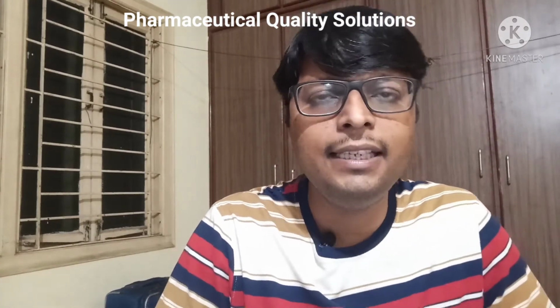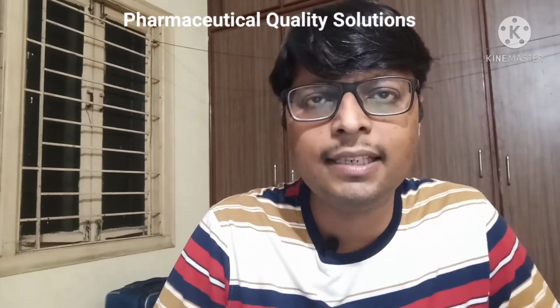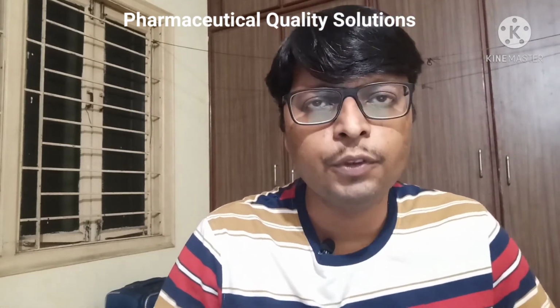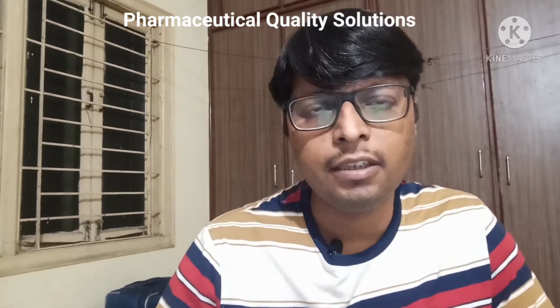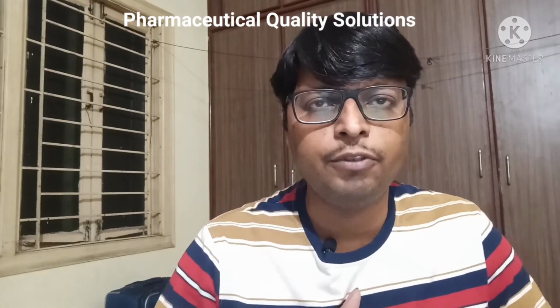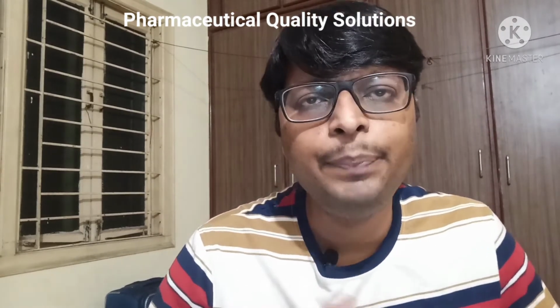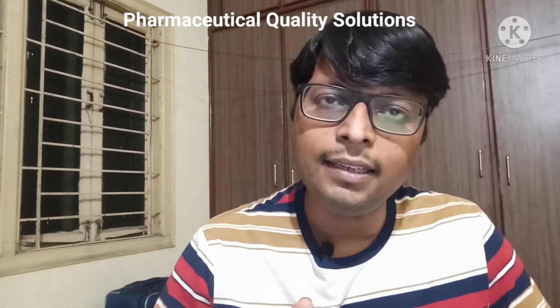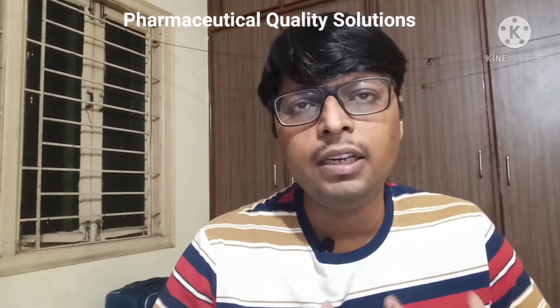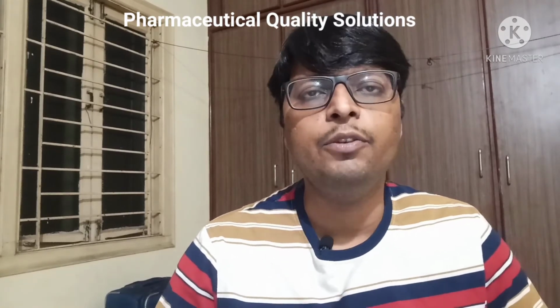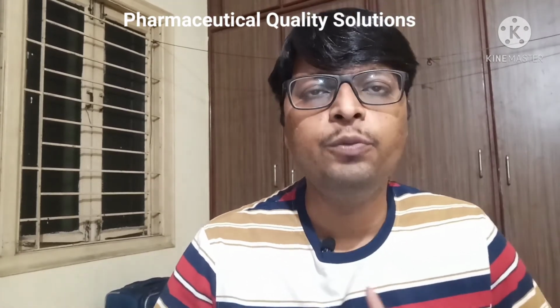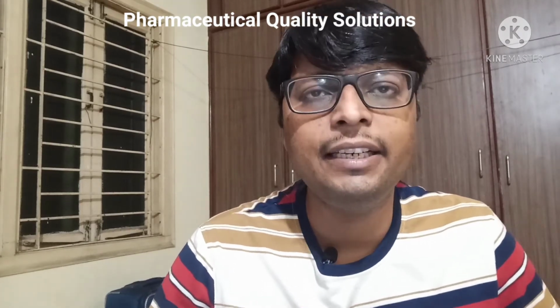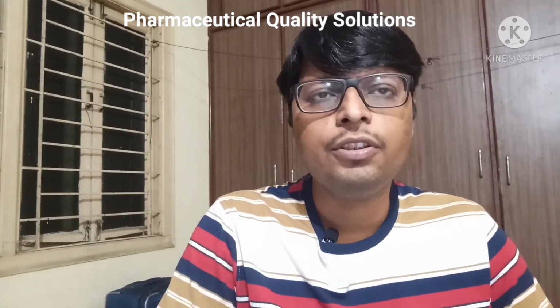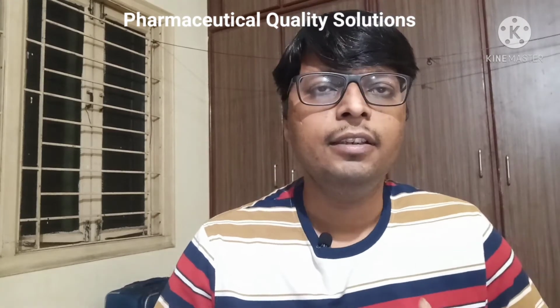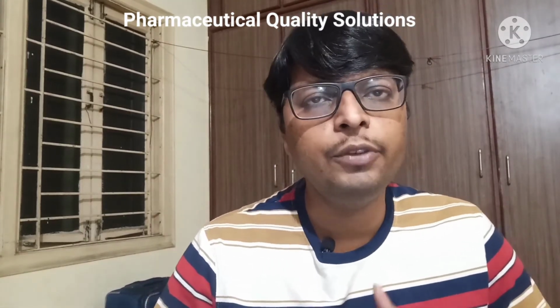The next category is Group B. These instruments give you results and they require calibration also, but they are not that automated and do not have much software. Like a pH meter or analytical balance, these come under Group B. Now Group C covers all the other instruments with complex software, like HPLC, GC, IR, UV. These instruments must have operations and calibrations, and they give you values. So the requirement will be taken care of. So guys, this is how we can categorize instruments into three.